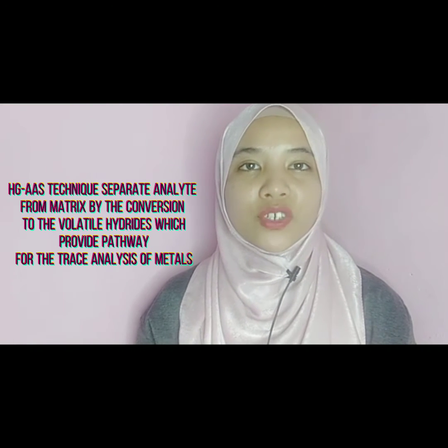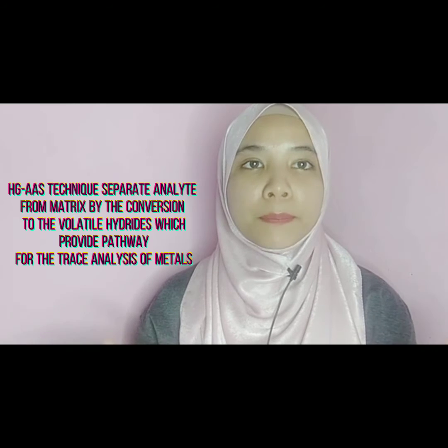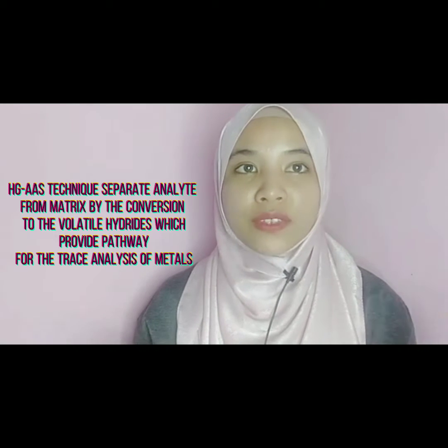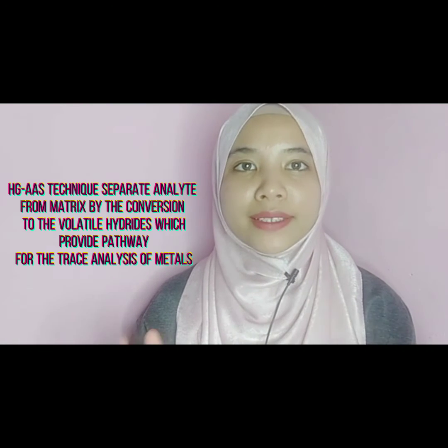the recoveries. Basically, the flow rate of the reagent and sample is affected by the tension on the peristaltic pump and also the size of tubing. So, the hydride generation technique separates the analyte from the matrix by conversion to the volatile hydride, which provides a pathway for the trace analysis of the element, which can be determined by the conventional method.